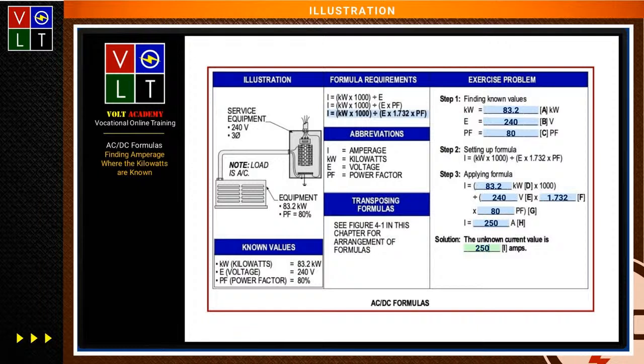Now, in this one, the kilowatts is 83.2 kW. You got 240 volts, and the power factor is 80%. You go over to step one, just put your values in. Then you're going to take that 83.2 and multiply it by 1,000. In other words, we're going to put it in VA form. And then we're going to take the 240 volts. It's a three-phase load, so I got to take that at 1.732, which will give me 416 volts. Then multiply that by 80% power factor, divide that into your 83.2 times 1,000, and that's going to give you 250 amps. Right. Okay.